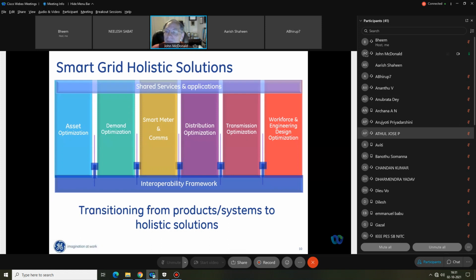So you can see if we use SCADA data, it's every 2, 4, or 6 seconds. But with synchrophasors, 40 to 50 samples per second. And that gives us a lot more insight into the behavior of the grid. And to finish my comment, if it's a SCADA system for distribution, this is where it's called a DMS or an ADMS. And we'll talk more about an ADMS.